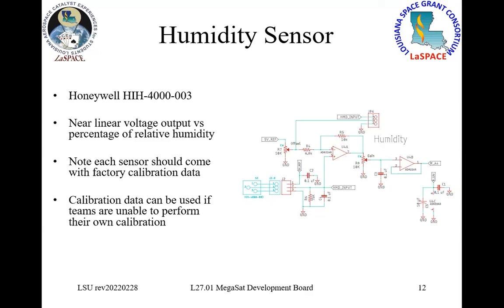I mention this because temperature sensors are relatively easy to calibrate. Pressure sensors can also be easy to calibrate if you have something like a small pressure-cooker style vacuum chamber, or a hand pump you can hook up to the sensing port. But humidity calibration is a lot trickier. The usual way you do a humidity calibration is by using various kinds of salt.